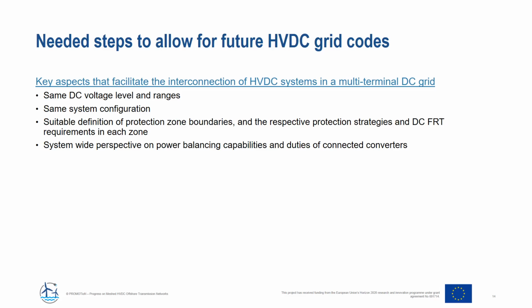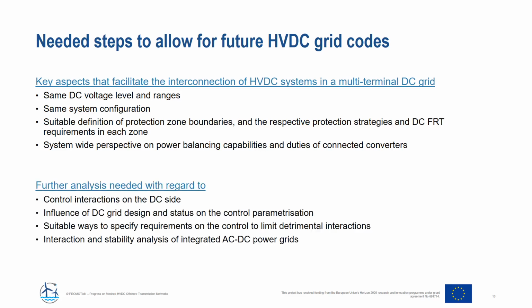Moreover, there needs to be a wider system perspective on, for example, power balancing capabilities and duties of connected converters. For example, when it comes to energy balancing and frequency support, the required energy has to come from somewhere and it has to be defined if this is from an offshore wind power plant or a connected asynchronous zone. While there's no DC grid code available, the integration of several DC systems needs a lot of studies, for example, EMT studies, interaction studies, hardware-in-the-loop control studies with replica system, to ensure that there's no detrimental interaction between the systems.